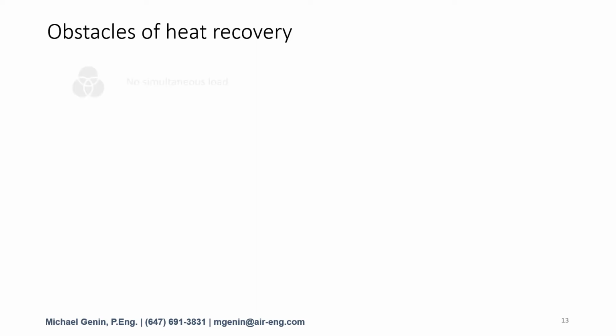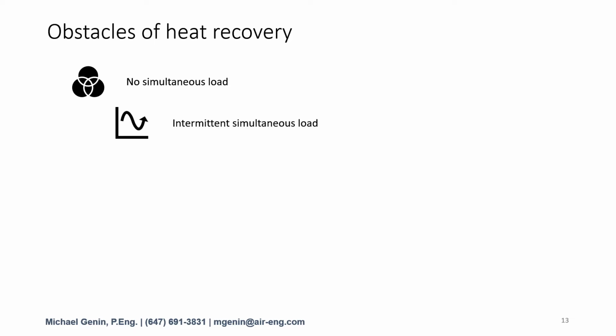So the first is no simultaneous load. This means no opportunity for heat recovery. Many buildings will not have a simultaneous load all of the time, but all buildings will have at least some kind of simultaneous load, even if it's extremely intermittent. Fine, we have a simultaneous load, but it's extremely intermittent. There is some load, but it doesn't happen all of the time.